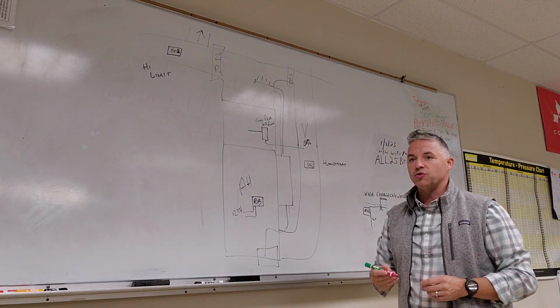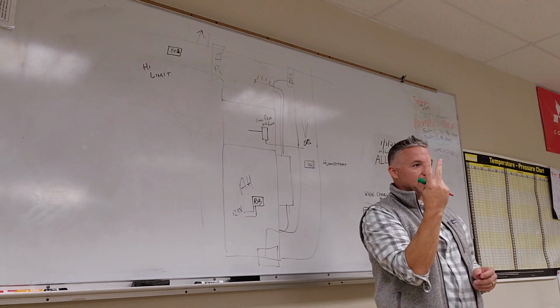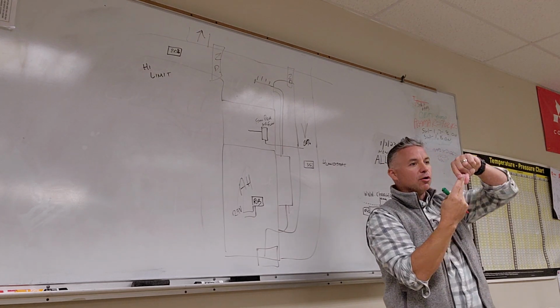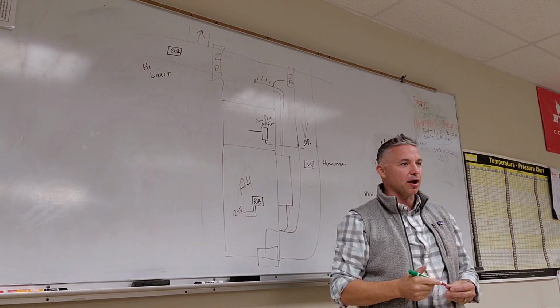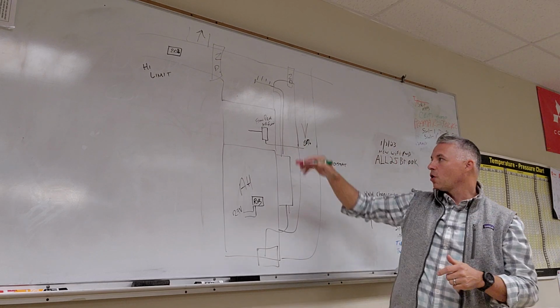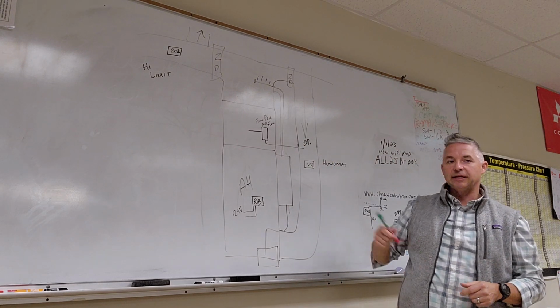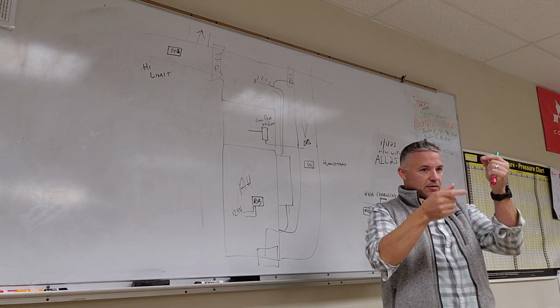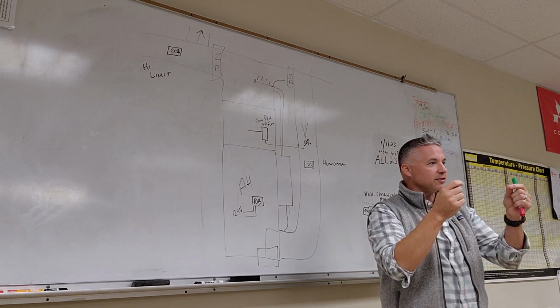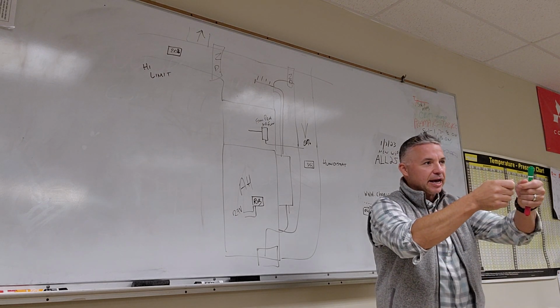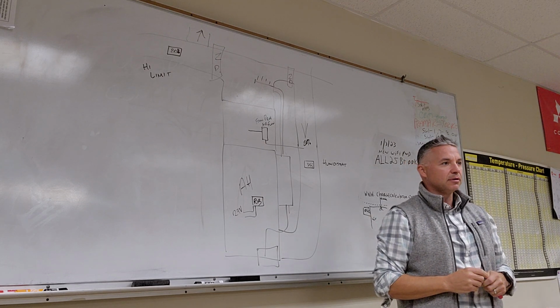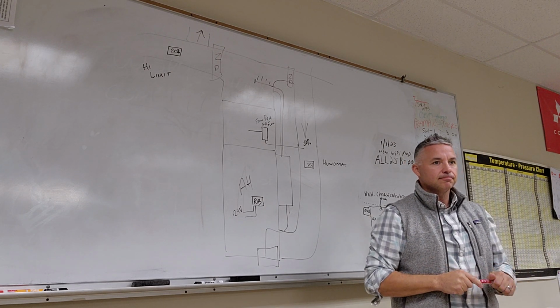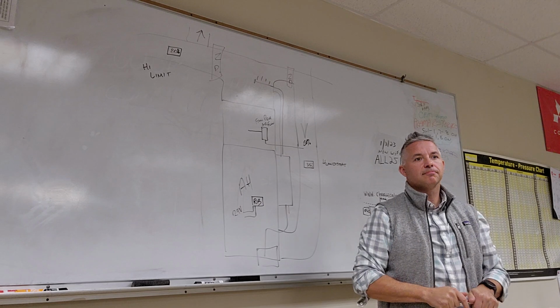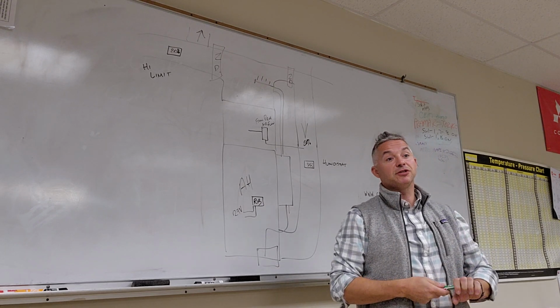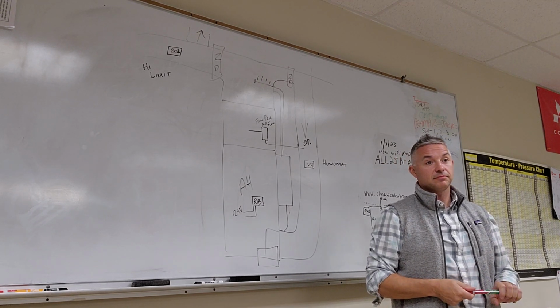In order to run that steam humidifier, there's one set of contacts in there that's open. And if we close those contacts, that steam humidifier is going to run. If I don't put any of those controls together and I just went into that steam humidifier and stripped down two ends of a small piece of wire and plugged them into those connections, that steam humidifier is going to run. You're also starting to see a lot of the modulating controls too, because all those steam humidifiers have the capability of modulating. Yeah. And you're seeing a lot more of that these days.